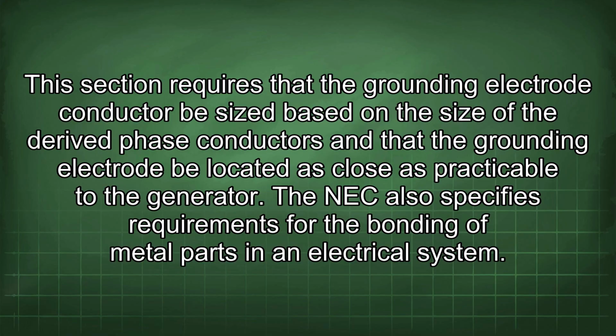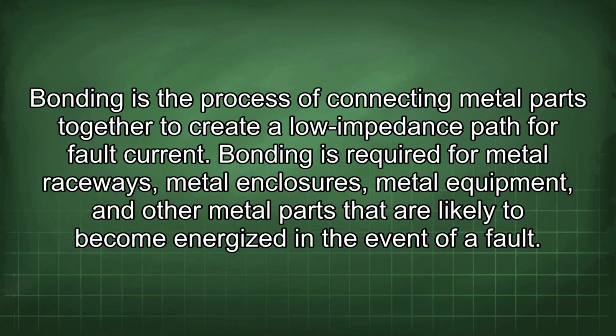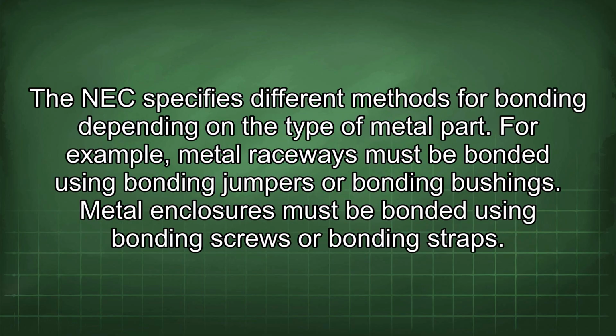The NEC also specifies requirements for the bonding of metal parts in an electrical system. Bonding is the process of connecting metal parts together to create a low impedance path for fault current. Bonding is required for metal raceways, metal enclosures, metal equipment, and other metal parts that are likely to become energized in the event of a fault. The NEC specifies different methods for bonding depending on the type of metal part. For example, metal raceways must be bonded using bonding jumpers or bonding bushings. Metal enclosures must be bonded using bonding screws or bonding straps.